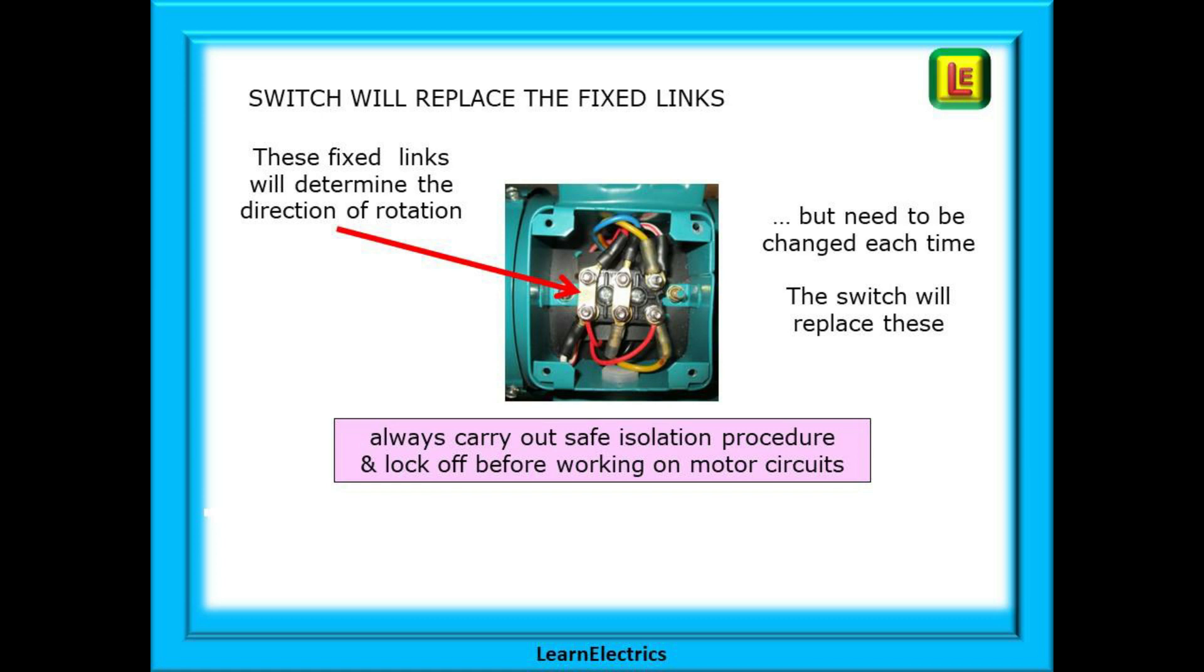Before you do any work on a motor circuit carry out safe isolation and lock off the circuit and allow capacitors enough time to discharge properly and this can take 30 to 60 seconds from switching off. Touching the terminals of a fully charged capacitor is certainly an attention grabbing experience.